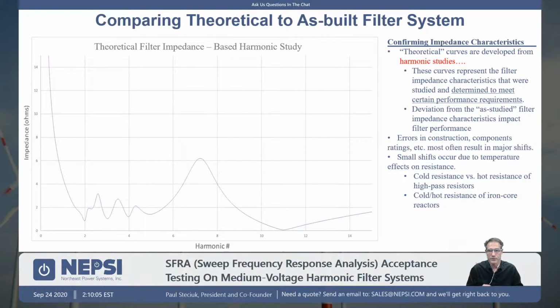When you look at a typical, and this is for this complex harmonic filter system, there was a harmonic study that was conducted, and that harmonic study came up with a filter design, and that filter design was put into the power system model, and then the expected performance was discovered or looked at and determined. So the question for the most part is, after we build a filter, how far did the impedance profile of the harmonic filter deviate from the study? All right. If the impedance profile is different, then the results that the study provided would be different.